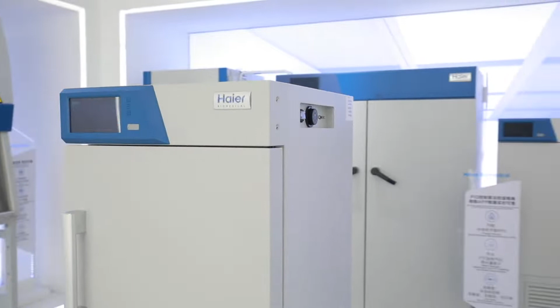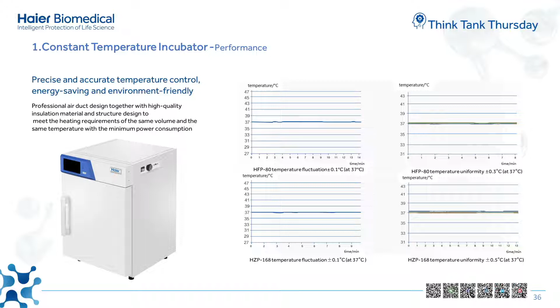From the 4 graphs on the right, we can see we have very stable temperature control in our product, because we're using an unequal PID algorithm and 4 heating machines. The double door and double ceiling structure design ensures the unit achieves a stable, high precision controlled environment. The temperature uniformity of HFP-80 is plus and minus 0.3 degrees, and HZP-168 is plus and minus 0.5 degrees.